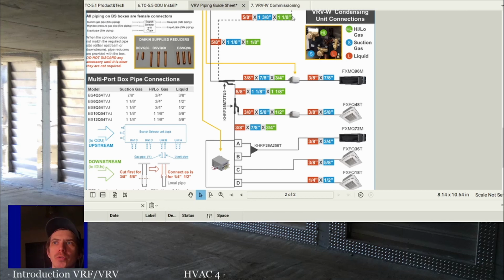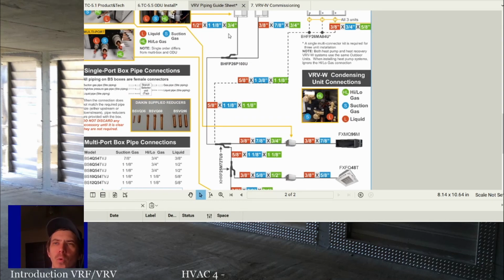It always goes one long wire from the outdoor unit to the first branch selector, and then one wire going from there to there. If this wire gets cut, pull a whole new wire from one to the other. Try to never splice the wire. You can get away with splicing the wire, but you're taking a risk, okay?